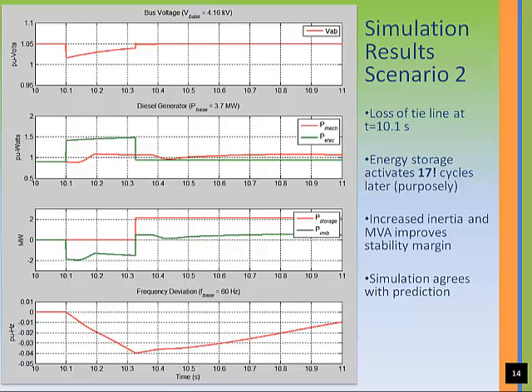As before, the top chart shows the generator bus voltage dropping due to the increase of load exerted onto the generator. The second chart shows in green the electrical power demand as seen by the diesel generator. As before, the red trace shows the governor takes about three cycles to respond. Chart three shows in red the energy storage becoming effective 17 cycles as predicted. The green trace shows the power imbalance experienced by the rotor. The power imbalance or accelerating power dictates the direction of the frequency change.